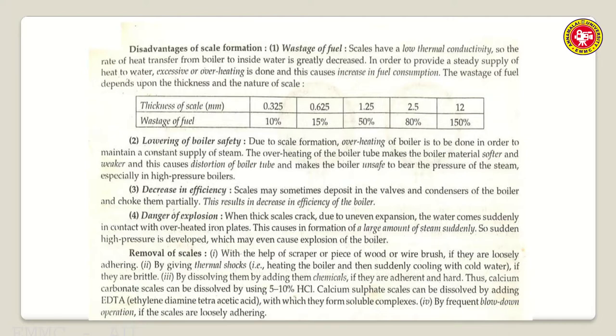Removal of scales can be done by rubbing heavily with a wire brush or by giving a thermal shock - heating the boiler to high temperature and then suddenly cooling it, causing the scales to detach from the surface. You can also use chemicals: for calcium carbonate scales use 5-10% HCl solution; for calcium sulphate scales use EDTA solution. You can also use the blow-down operation.